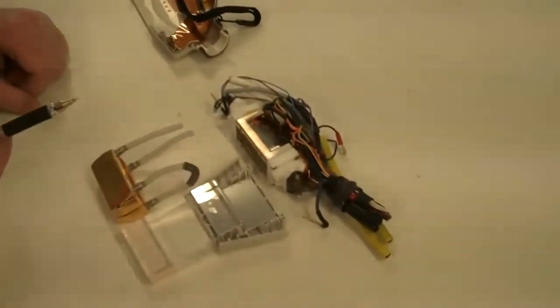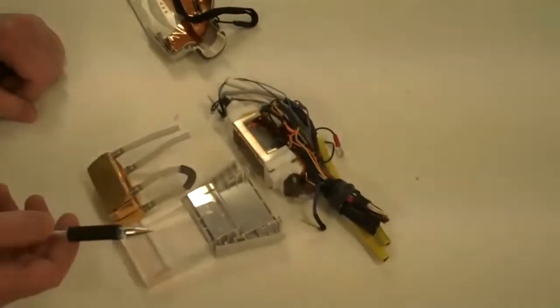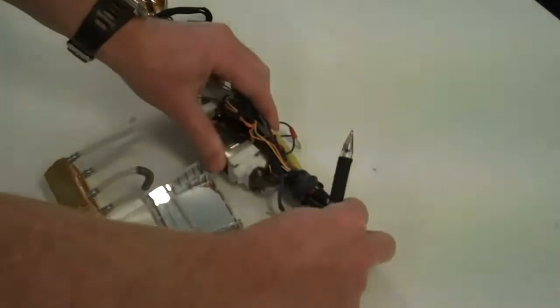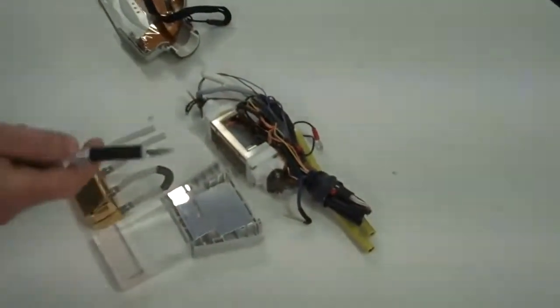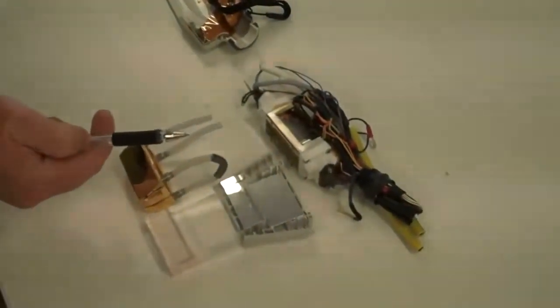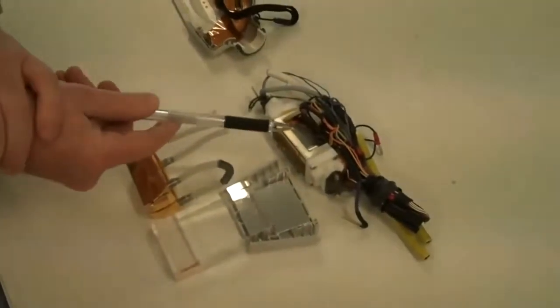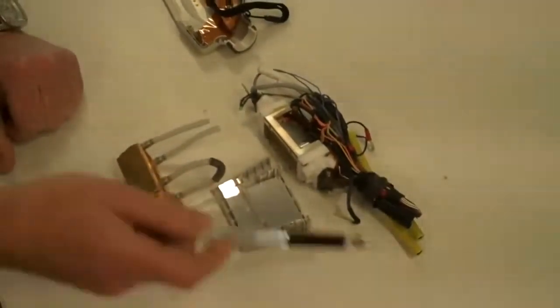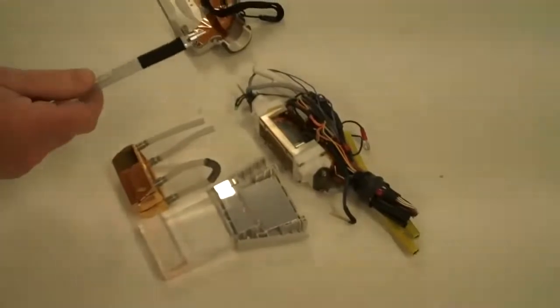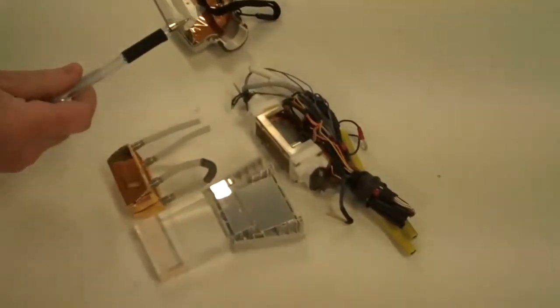The other important factor is that because it's only 3 months old, you don't have all the years of flexing, which could also cause intermittent faults and random faults, which can not only damage the handpiece, but could also spike back and damage your base unit as well. And this is very, very common that I've seen out in the market.